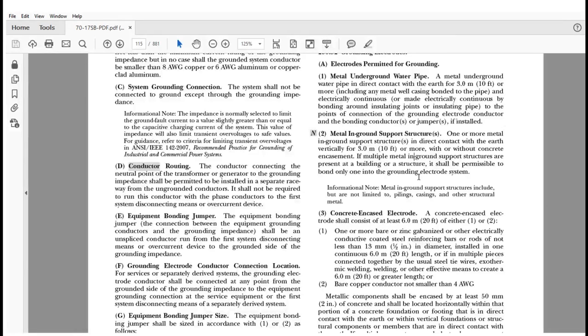Now, just to remind you, because sometimes people want clarity on this, it shall be permissible to bond only one of the in-ground support structures into the grounding electrode system. Not every one of them. You still need the 10 feet vertically or more, and it doesn't matter whether concrete is in there or not, whether it's encased or not. If this is like a support piling that's driven down and it's steel, then that can be utilized.